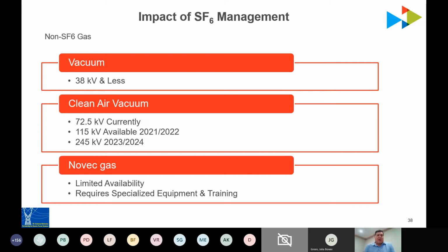Our non-SF6 equipment options are vacuum, clean air vacuum, or just vacuum. As I said earlier, 38 kV and less is complete vacuum technology. We're currently using, employing, and implementing the 72 kV clean air vacuum dead tank breaker from Hitachi, and we're looking at other manufacturers coming on board with additional equipment.